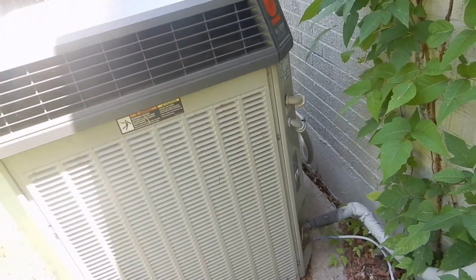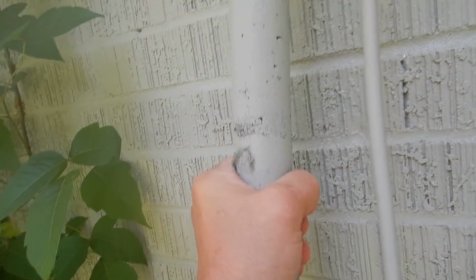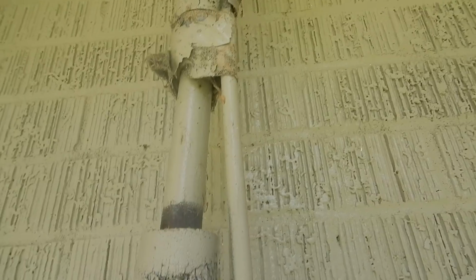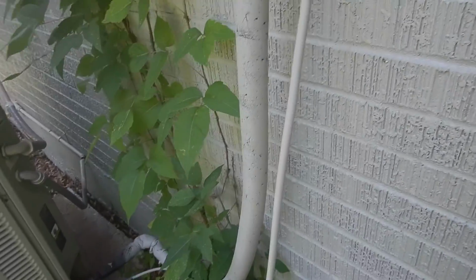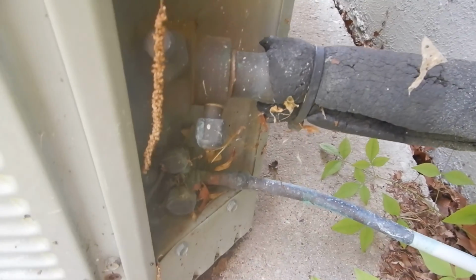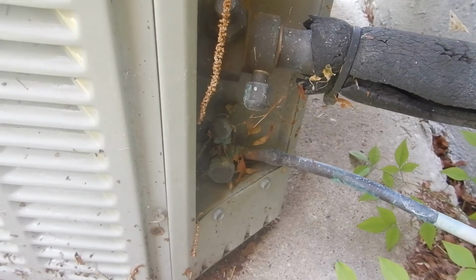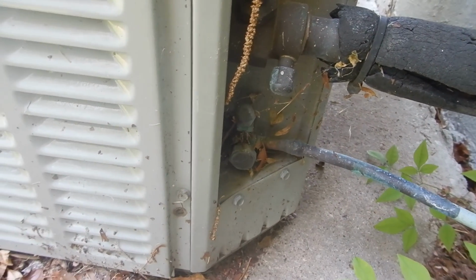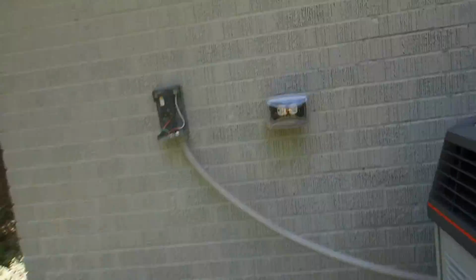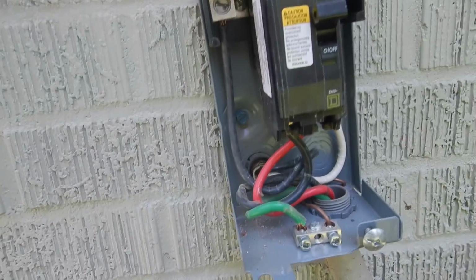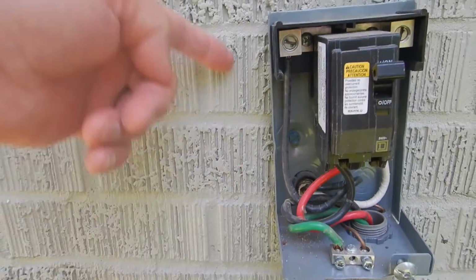Now, when this system was installed 20 years ago, this insulation on the low pressure line was fine. But by today's standards, it doesn't meet today's energy standards. But it's not supposed to be missing, so we're missing some insulation there at a minimum. It'd be nice if this were updated. Painting is not updating it. And again, this wasn't available until 2015, but our refrigerant service valve port caps, Schrader valve caps, are not anti-theft. The coils don't look that dirty. This is our electric service, and we have a receptacle outlet to service the unit. This is our main service disconnect, and it should be sealed like the electric meter. It should be sealed on 3 sides.